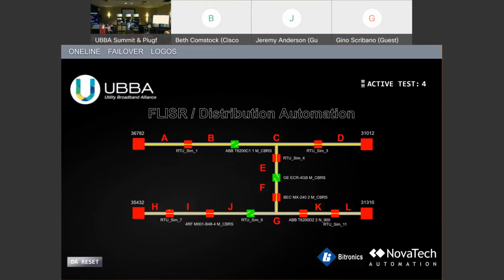Let's think about a manually motor-operated switch. You send the command, it usually acknowledges it's going to operate, but then it goes into an intermediate state, and we have to wait for that motor to move the switch blades out of the way. Eventually we get a signal back that the switch is fully open.